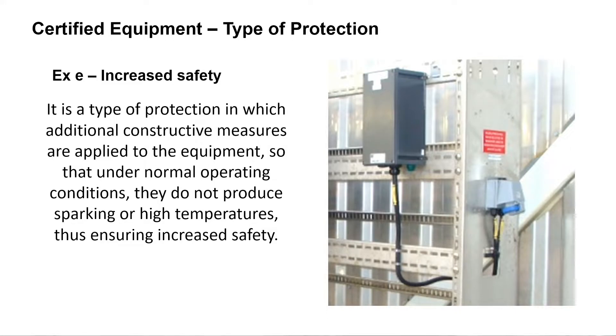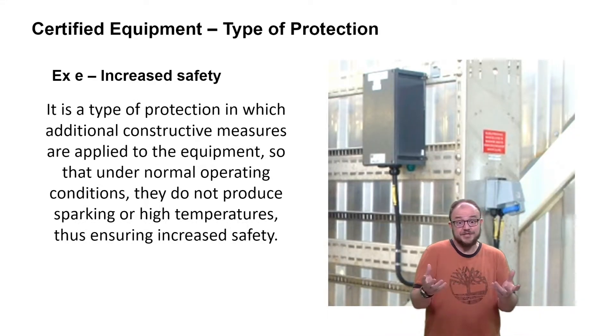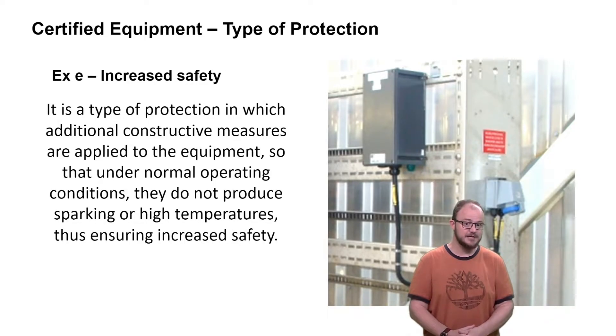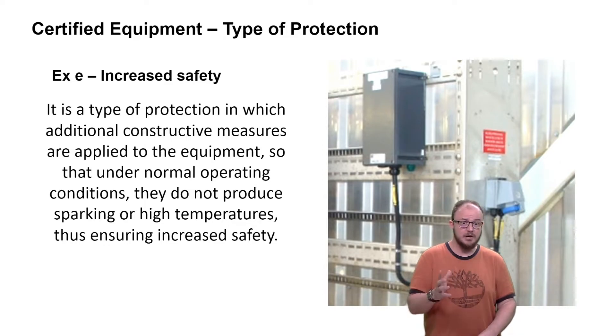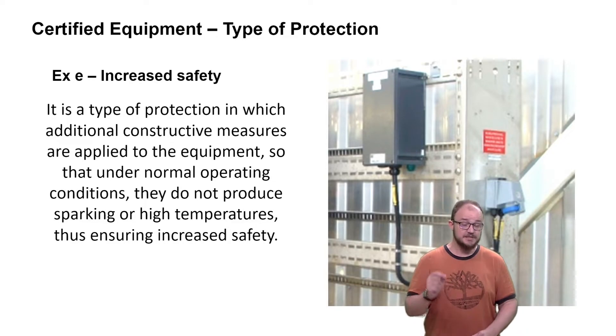The second one is the increased safety. They use special measures and constructive materials to assemble this equipment, and in normal operation they do not produce high temperatures or spark conditions, which are both sources of ignition. This equipment is very handy and commonly used because it can be made from a special plastic — not ordinary plastic — it's not heavy and can be installed in different places. It's a very useful, very handy type of protection.